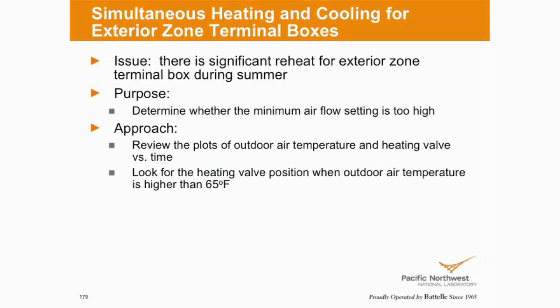Simultaneous heating and cooling for the perimeter zone terminal box. So if you find there's a significant reheat for perimeter zone terminal box during summertime, that's another sign tells you that you may have a minimum airflow set point too high. So we can review the plots of outdoor air temperature and the heating valve position versus time, and look at the heating valve position for the temperature is higher than 65 degrees.